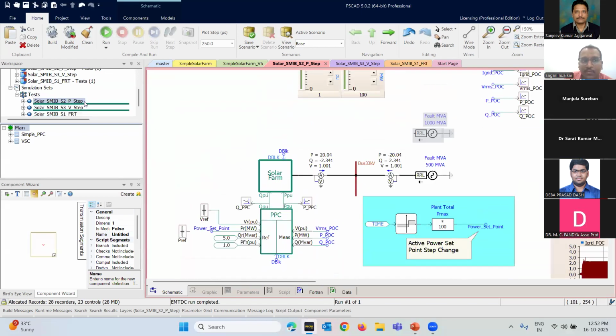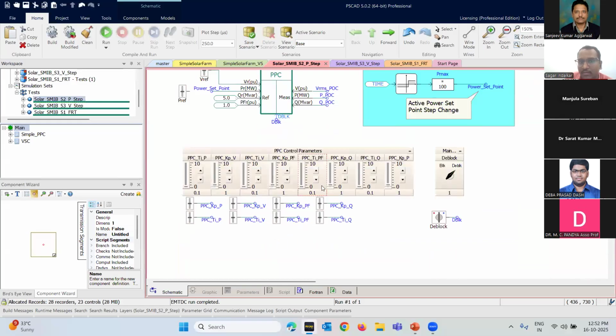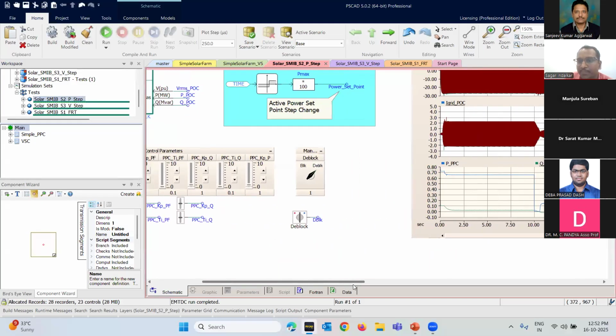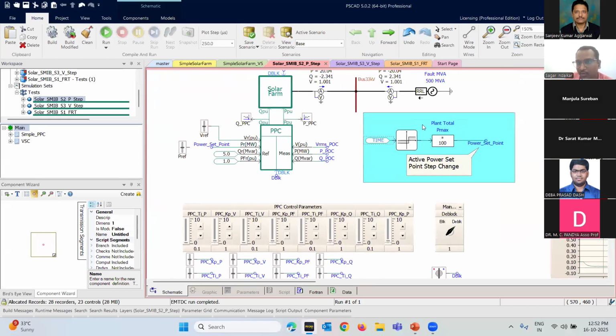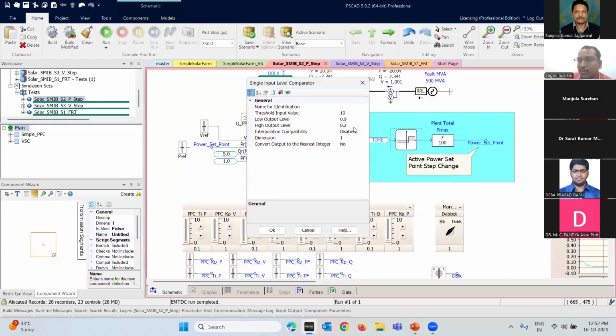So the number of tests which I discussed in the slide are again performed here. So what you have here is each step. In each step, you use this control logic. You're giving a time reference to a comparator. When the time crosses 10 seconds, it will change the output from 0.9 to 0.2. So at 10 seconds, my P set point to the PPC will reduce from 0.9 to 0.2.